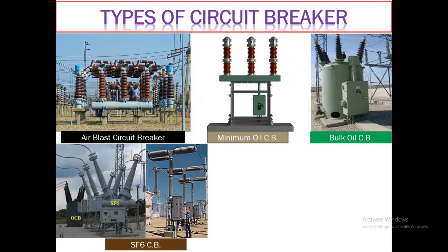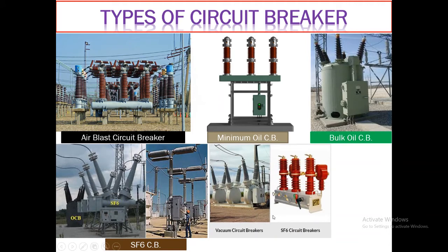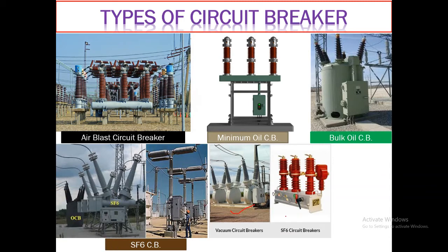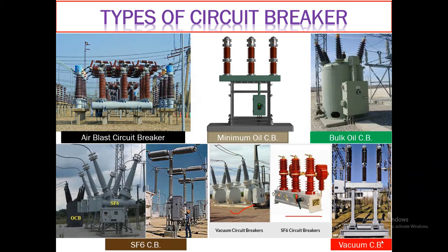This is again the photograph of an SF6 type circuit breaker. On the left side of this photo is the vacuum circuit breaker, and this is another design of an SF6 circuit breaker. Sometimes the vacuum circuit breaker looks quite similar to the minimum oil circuit breaker, but if you look closely at the top you can identify it: on the oil type, there is a gauge representing the oil level, which is not present on the vacuum circuit breaker.